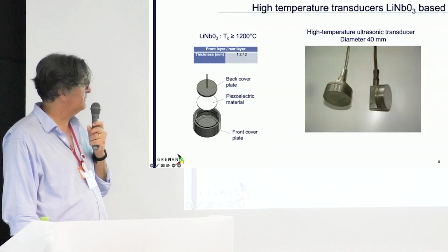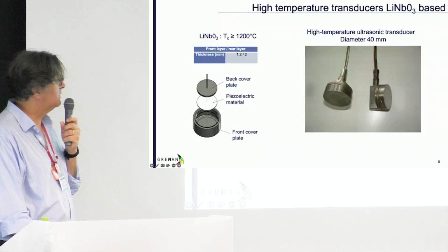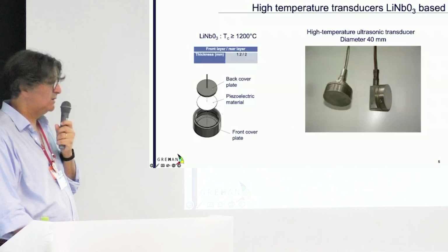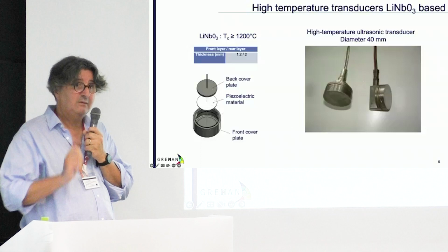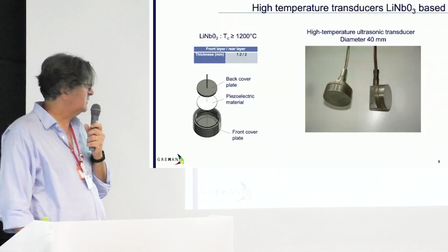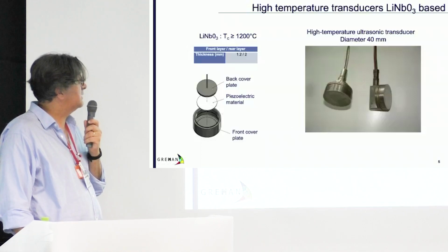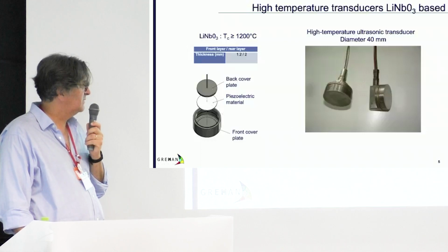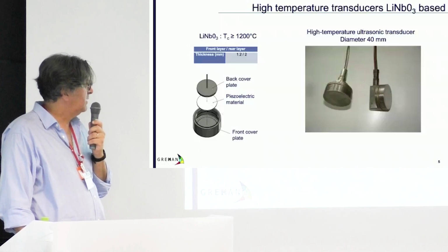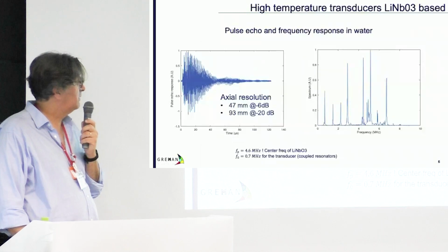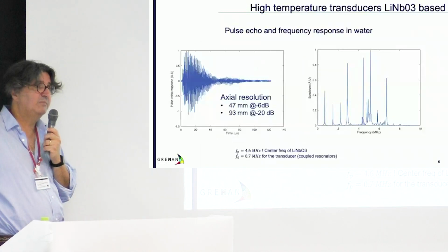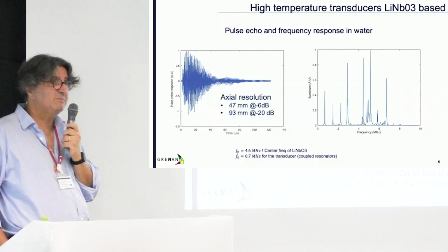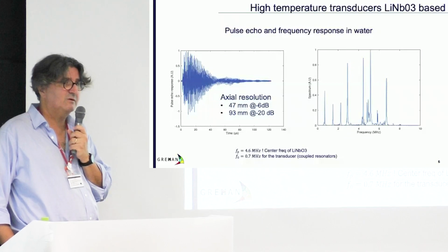Here, for instance, you have a picture of a high temperature ultrasonic transducer. That's quite nice. It supports high temperature, up to 300 degrees, 400 degrees, even higher. But there is one problem. This is a pulse echo response and the frequency spectra of such a transducer.